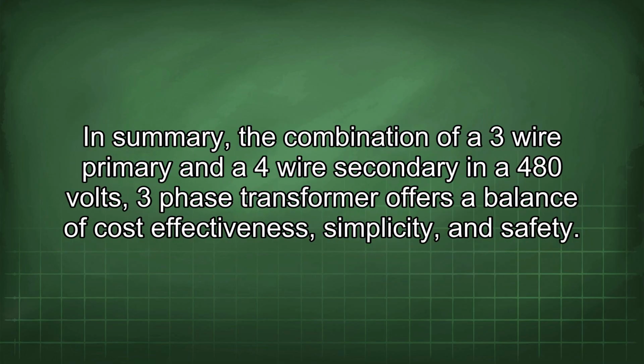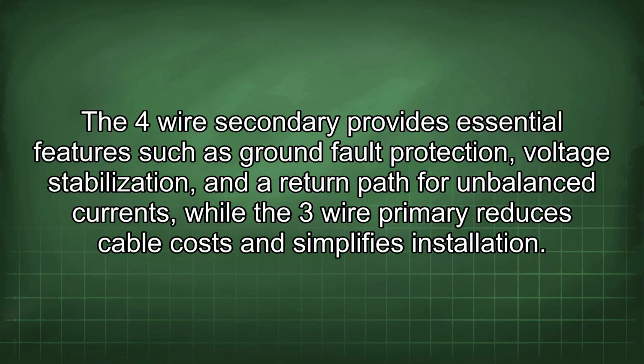In summary, the combination of a 3-wire primary and a 4-wire secondary in a 480 volts, 3-phase transformer offers a balance of cost-effectiveness, simplicity, and safety. A 4-wire secondary provides essential features such as ground fault protection, voltage stabilization, and a return path for unbalanced currents, while the 3-wire primary reduces cable costs and simplifies installation.